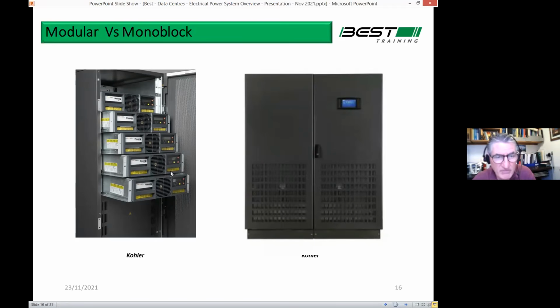So this system on the left, this modular way of doing it, is far better. It's much more energy efficient. You can buy the modules and build it up as time goes on. The availability is much higher, which means basically if one of these units fails, you literally just whip it out like any piece of equipment. It's plug and play. You whip it out and replace it with another one. If this unit fails, you have to shut the whole unit down, start pulling parts out, like repairing your engine in the car or something. It's a fairly big job. So the downtime of these can be much higher than this system, and as a result, the availability is lower. So for lots of reasons, the industry is moving over to this modular design arrangement now.